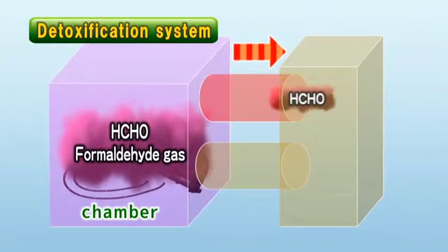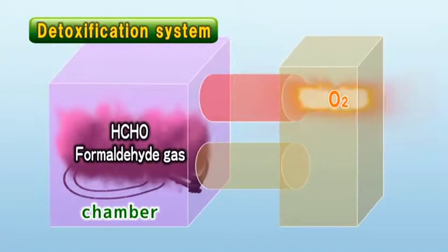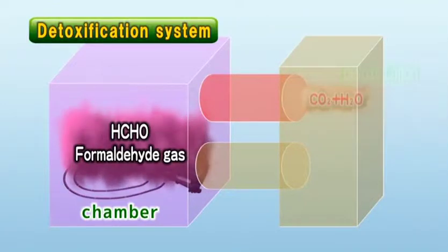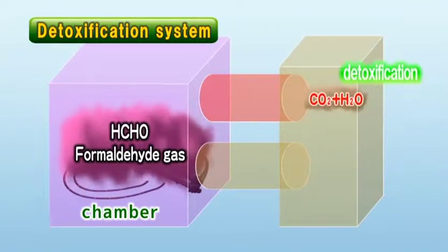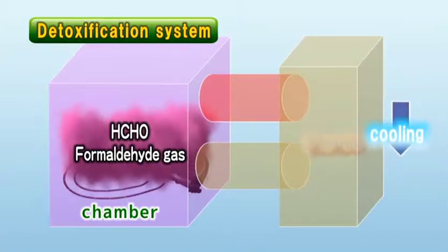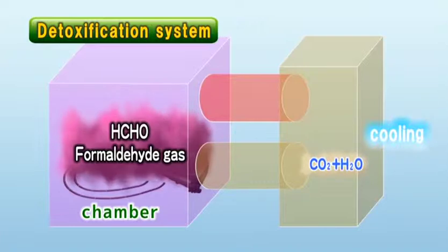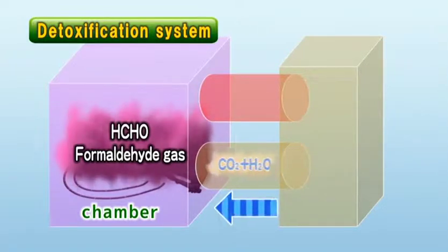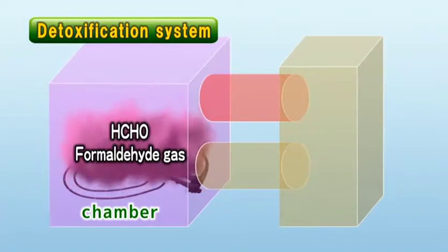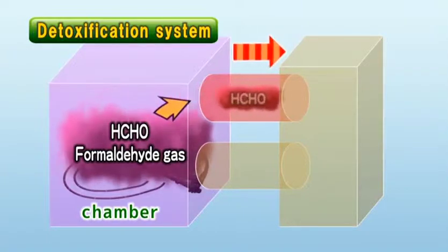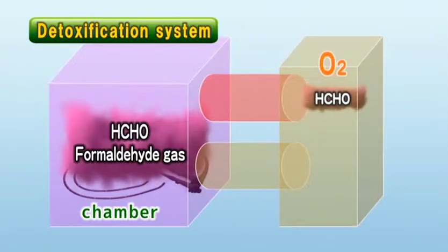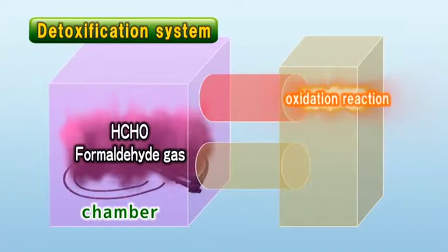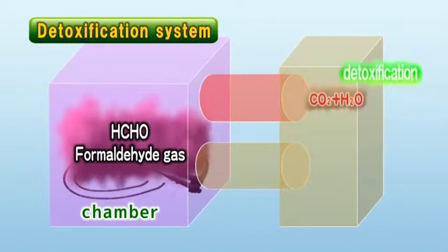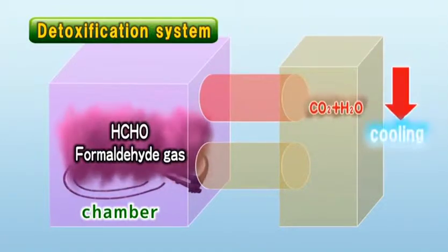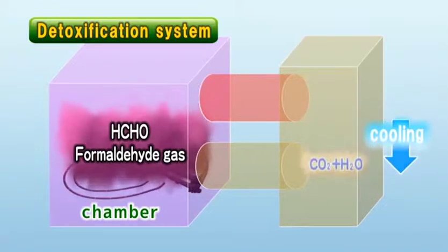The formaldehyde gas used in the chamber undergoes catalytic oxidation and is broken down into carbon dioxide and water vapor, becoming no longer toxic. The high-temperature combustion gas generated in the process of oxidation reaction is cooled and then returned back to the chamber. Formaldehyde gas will no longer be toxic after repeating this cycle. This state-of-the-art technology of breaking down and detoxifying formaldehyde gas is drawing international attention.